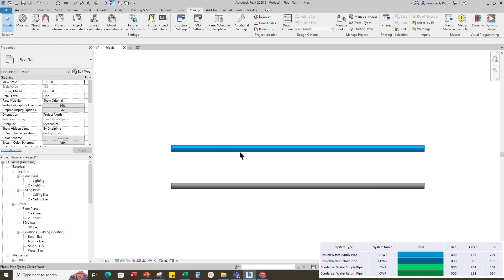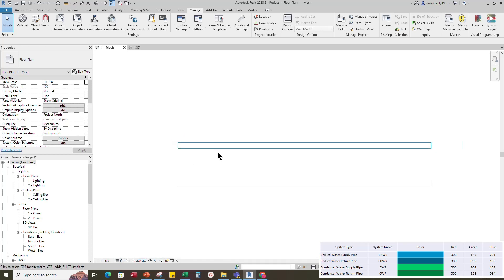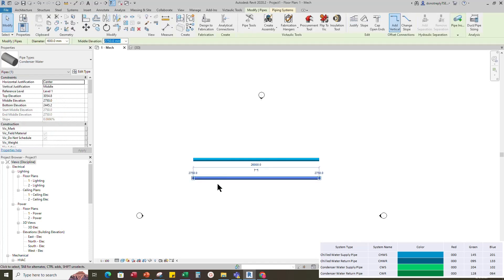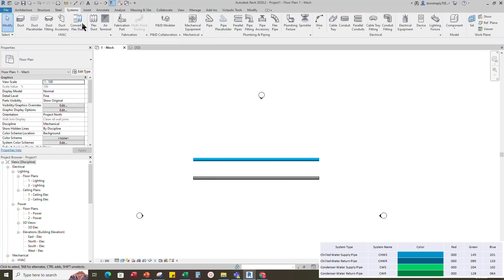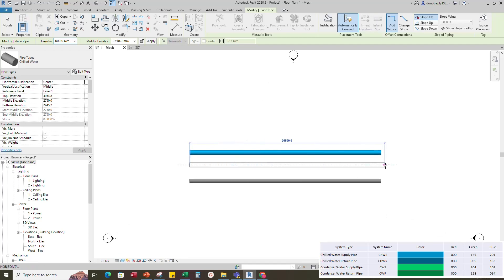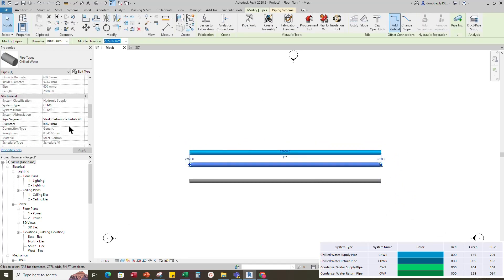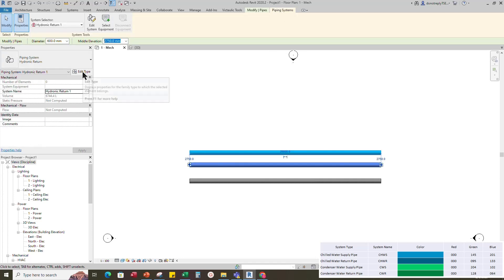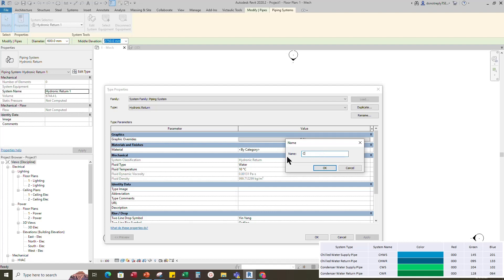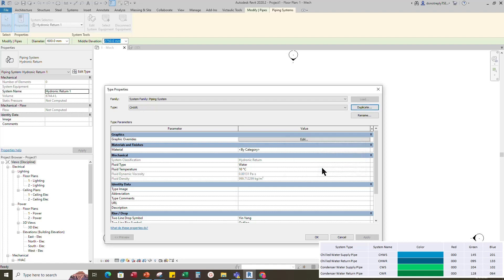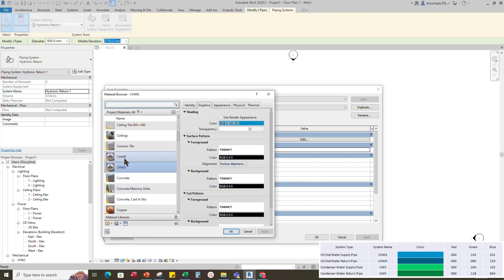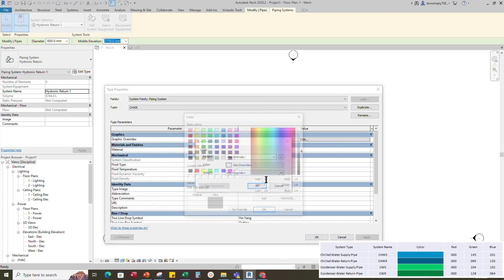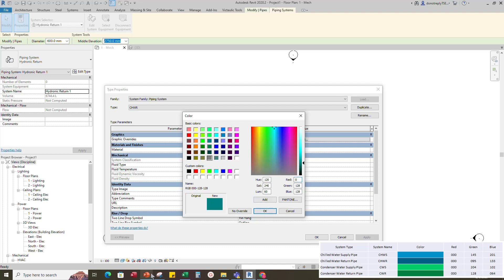Check in the wireframe view — the color has changed. Go to System and draw a new pipe for the chilled water return pipe. Select the pipe and change the pipe system type to Hydronic Return. Select the hydronic return pipe, go to Piping System and Edit Type. Duplicate the hydronic return and rename it to chwr. Add material by category to chwr. Change the RGB color code for the graphic override. Set line weight to 1 and click OK.